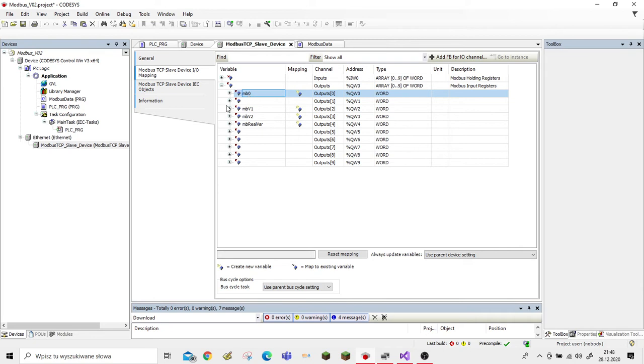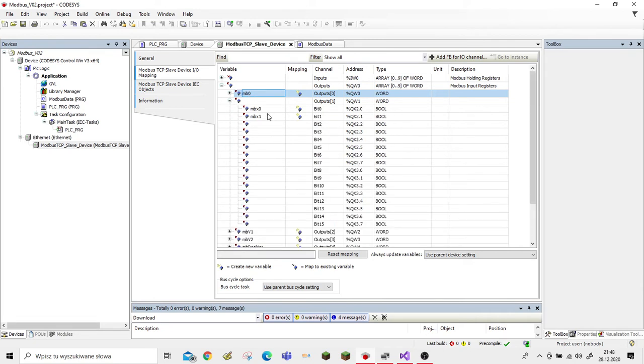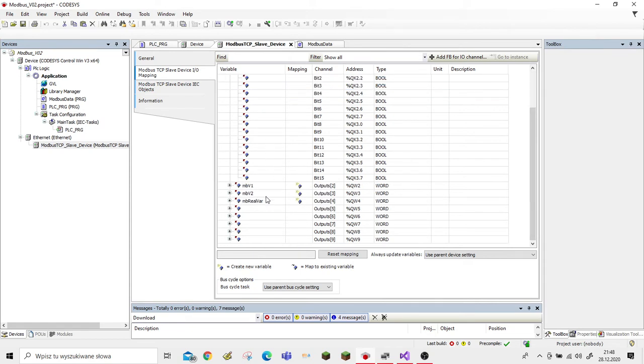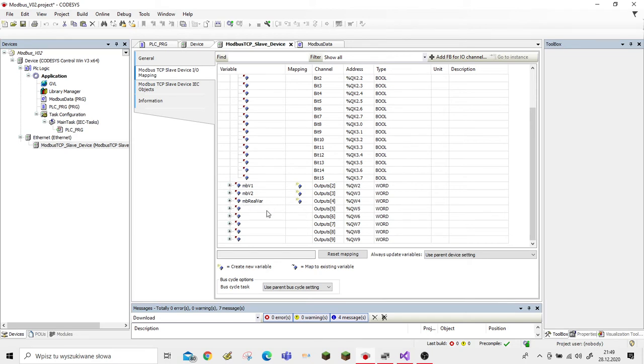I have declared here variables: one word variable mb0, and also bool variables mbx0 and mbx1. These variables I will be using to send a REAL variable over Modbus protocol. A REAL variable consists of four bytes, so we have to send it in two words: mbv1 and mbv2. There is also a word variable called mbRealVar, which we will also use to transfer a REAL variable — we will talk about that later.